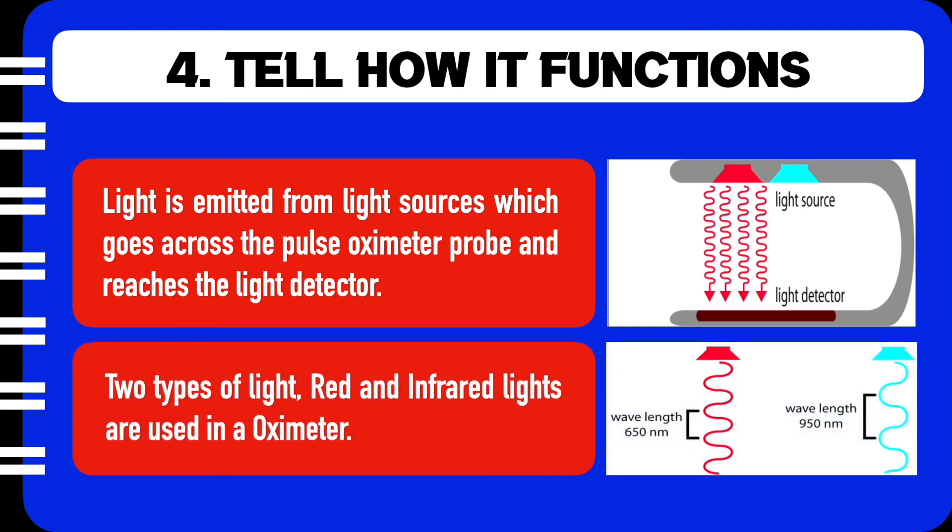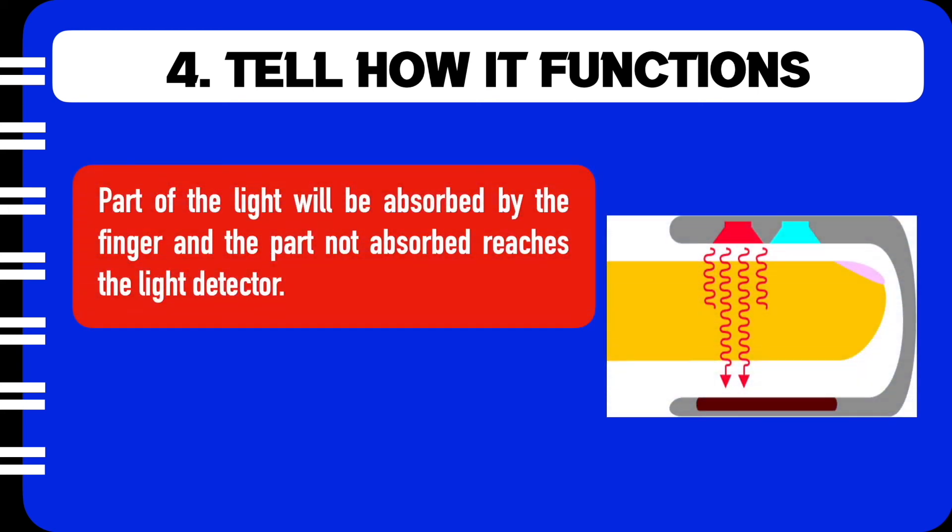Now two types of light, red and infrared lights, are used in an oximeter. When you place a finger in between the light source and the light detector, the light passes through the finger and the tissues in it to reach the detector. A part of the light will get absorbed by the finger and part which is not absorbed reaches the light detector.